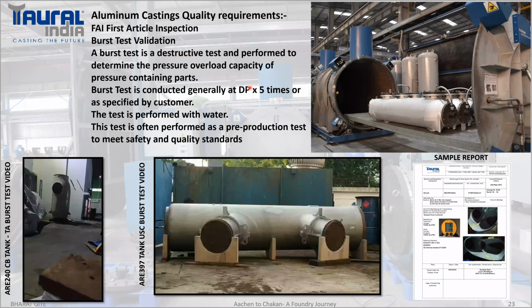So 7 bar is the design pressure and 5 times is 35 bar. Usually our castings burst at 70 bar and above, and sometimes the flanges come out because there is no damage on the casting structure. This is possible only because of the casting methodology, state-of-the-art process, and the know-how made in Europe. Not to forget, our best friend Magmasoft from Aachen helps us to reduce our stay at the Gießhalle, at the casting floor. So I will play the first casting burst test.